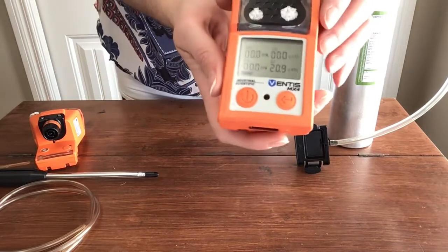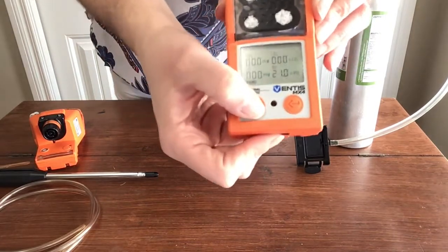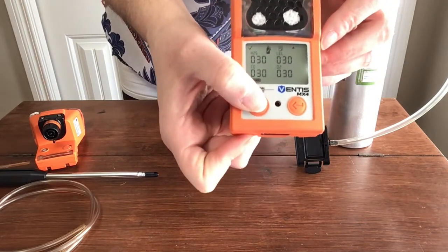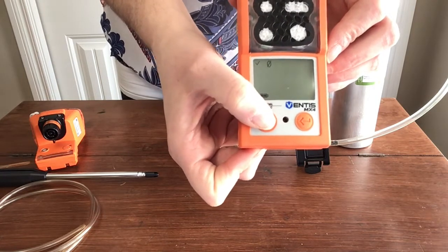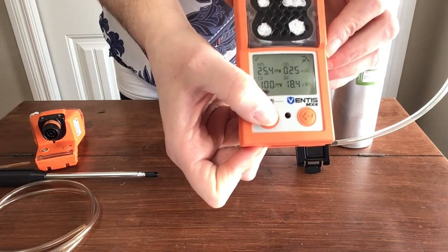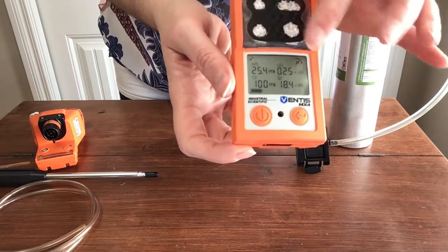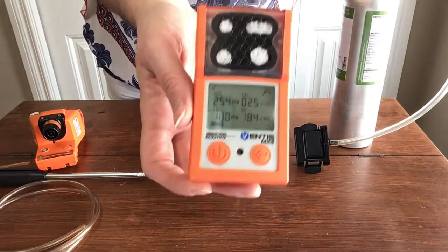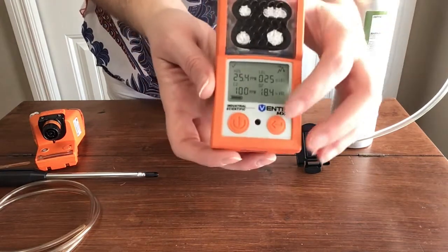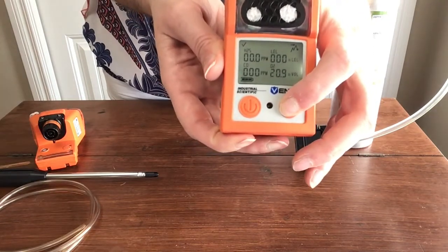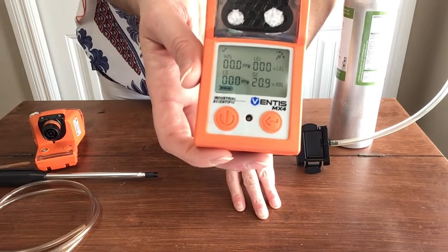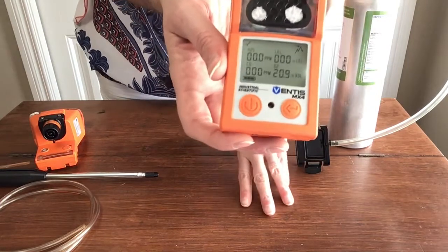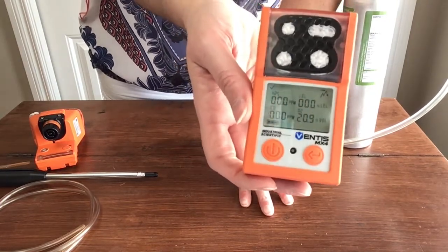The last thing that you want to do though, before you actually use this, is you want to go clear those peaks. Okay, so now you can see that our calendar has changed to 30. We have 30 days until our next calibration because we just calibrated it. And when we get to those peaks, you'll see that you now have peak readings on these gases. That's because I put the gas on it, right? And so before you have anybody take this into a work environment, we want to make sure that we actually clear these by pressing and holding until everything returns to normal. If you still have a couple numbers on here, it just means you did it too soon after you took the gas off, so just press and hold again, it'll go to 0. And now it's okay for a worker to take this to the workplace.